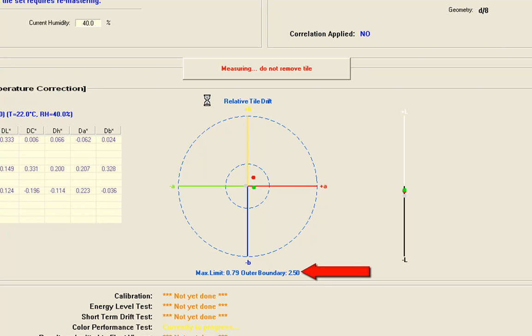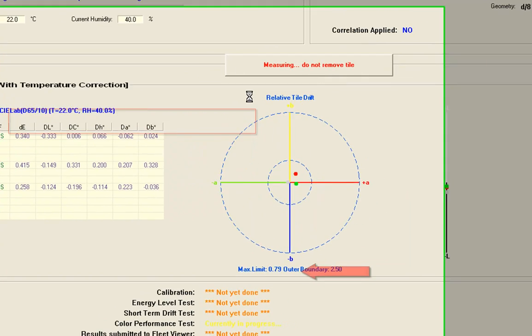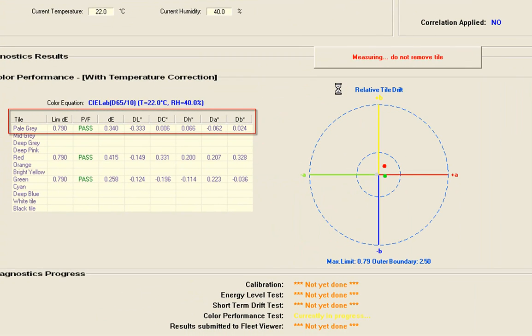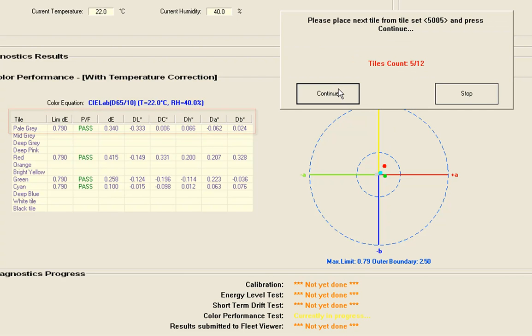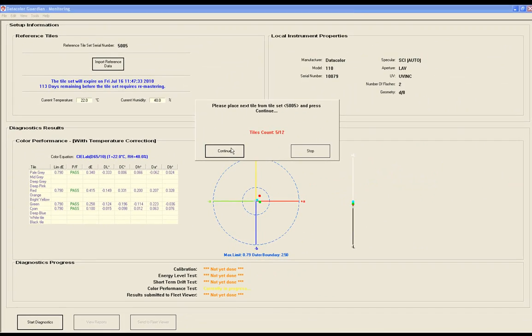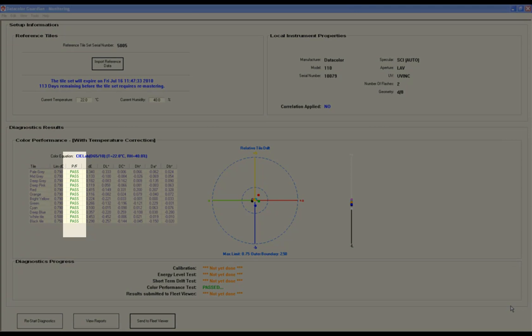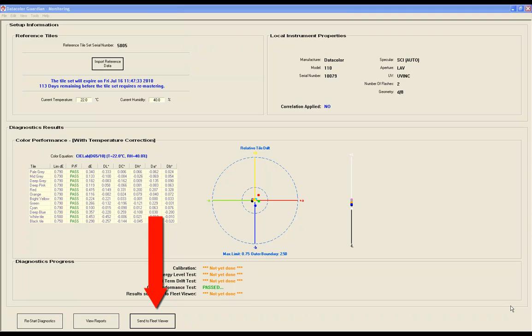Each instrument has its tolerances and they are automatically adjusted on the color circle. For each tile there is a pass-fail, limit delta E, actual delta E and other color coordinates. When the color performance test is done successfully, you can send the results by clicking the Send to Fleet Viewer button. Guardian will then send the results automatically to the mail address that is specified in the communication settings.